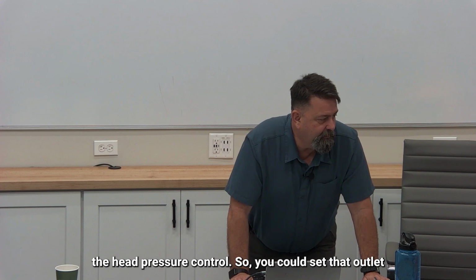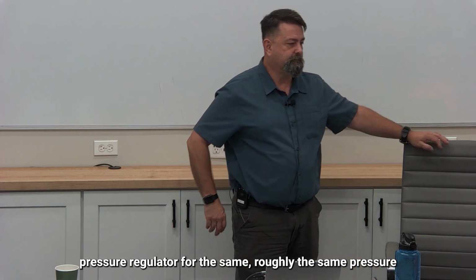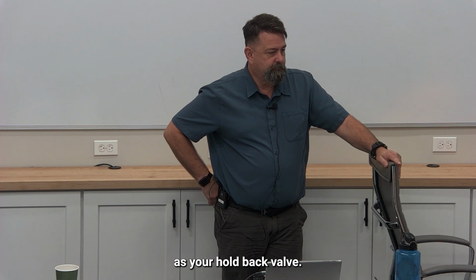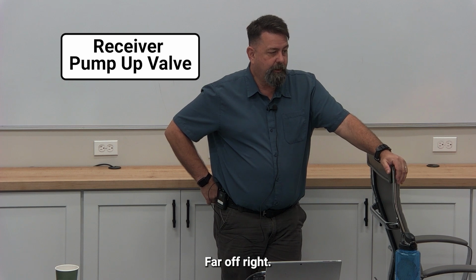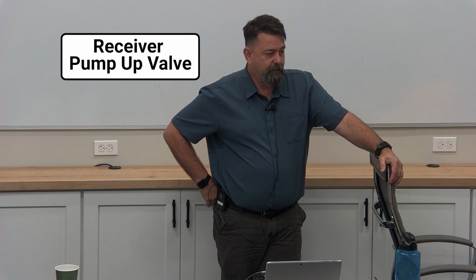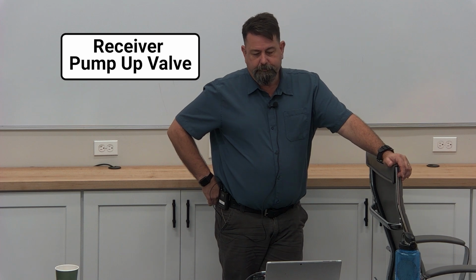Yep. So you could set that outlet pressure regulator to roughly the same pressure as your holdback valve. They're not going to be terribly different. Far off, right? Yep, 10, 15 PSI. Exactly. Okay, so just a practical example, let's say that artificial rack I just made up with 50 PSI suction, right? If my warmest evaporator was 50 degrees, 50 PSI was its setting, I would set this outlet pressure regulator to 150 pounds, right? And since I can go to 90, I could go to 140.